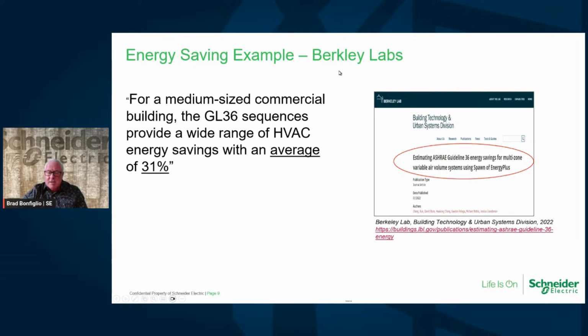I'm going to give you some examples of some folks that have worked on this doing a study. One of them was Berkeley Lab, where they actually looked at a medium-sized building. They found the average energy savings using Guideline 36 was 31%. When you look at building management, the rough rule of thumb has always been 10 to 15% energy savings when you use a BMS system. Well, this is 31%. So this is not a smaller number. This is a bigger number you're dealing with in these sequences.